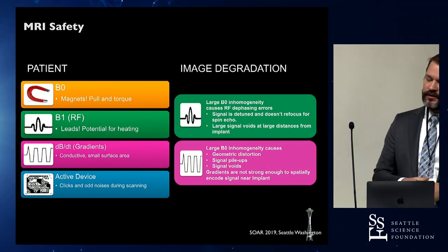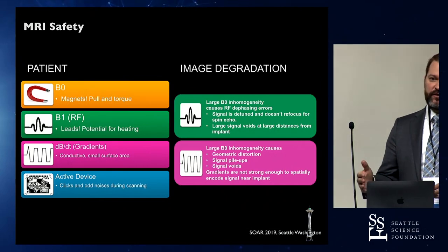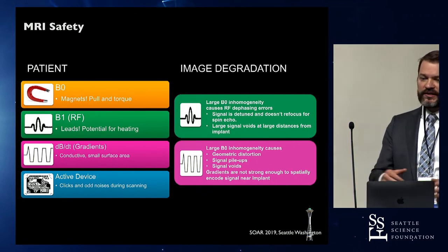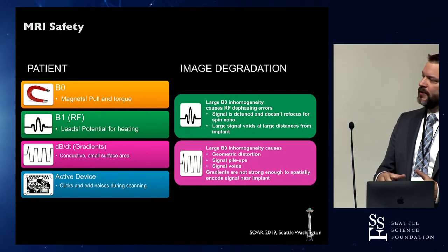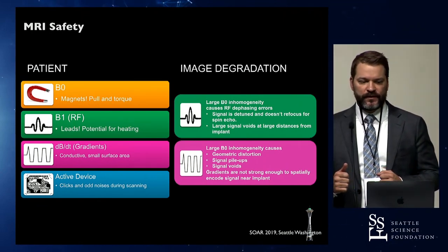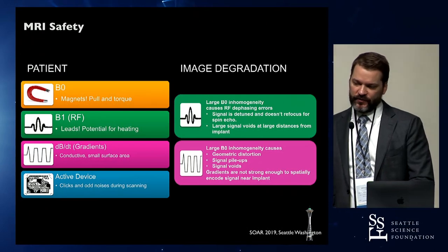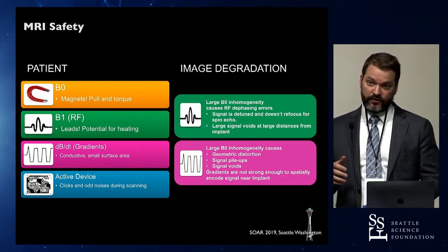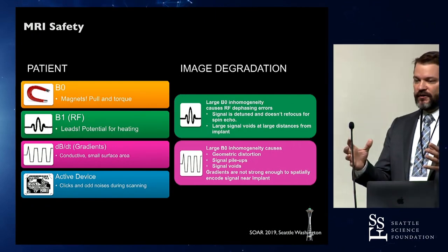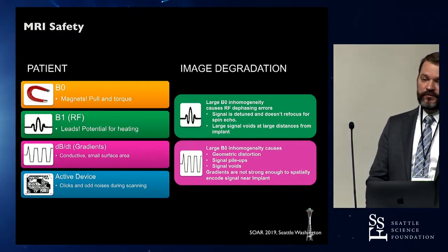The gradients can also affect the battery's charge and mess with the circuitry. Sometimes patients actually activate the device even though the external processor is off — they'll say they're hearing sounds in the scanner. Beyond device effects, a cochlear implant in a head scan can compromise scan quality. The magnet can interfere with the homogeneity of your static magnetic field and create a sphere of distortion around the device up to 10 centimeters away, potentially obscuring the anatomy of interest — such as a temporal GBM.